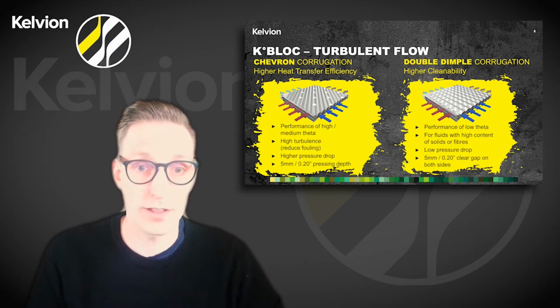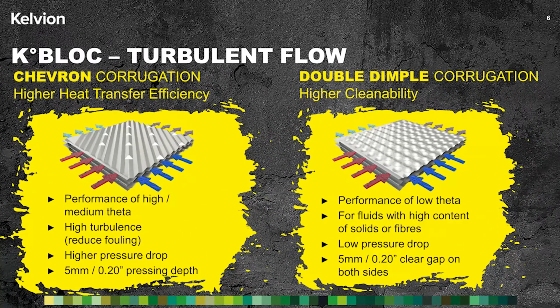The initially promoted efficiency of the K-BLOC is based on the plate geometry, which is the main enabler for the outstanding heat transfer. The K-BLOC comes with the standard and high-performing CHEVRON corrugation with increased turbulence. A higher grade of turbulence is beneficial for heat transfer and also for the so-called self-cleaning effect.